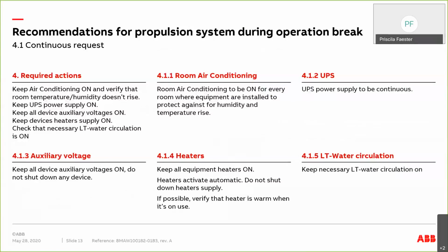As a continuous request for warm and hot layup, air conditioning should be on to keep the temperature and humidity at an acceptable level. UPS power supplies should be on to provide power for the electronics in all kinds of equipment boards. The auxiliary voltages should also be on if cooling fans are needed or water pumps need to be rotated. Heaters should be on to keep the temperature a little higher inside the equipment than outside, to avoid humidity coming inside. And LT water circulation should be on as well.